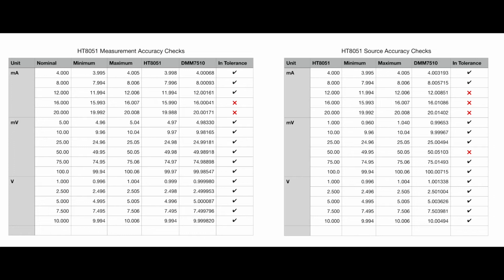out. Millivolt wise, there is one reading that's ever so slightly out for source mode at 50 millivolts. And so that could be a discrepancy in the measurement method when you get the oddball reading like that. In voltage terms, at the bottom of the tables there, they all look to be okay, all within tolerance. So that's the measurements that I made there.